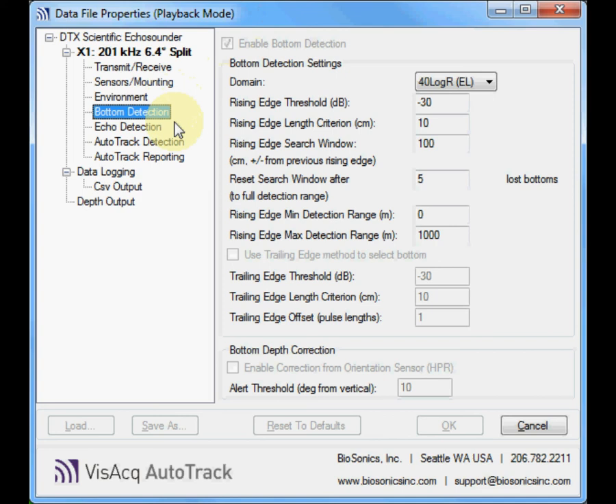Next is the bottom detection tab. While we don't have to have this enabled for collecting calibration data, it is useful for separating echoes from the bottom from all the other targets of interest when you're doing your analysis. So it's okay to go ahead and check this box and set your appropriate settings.